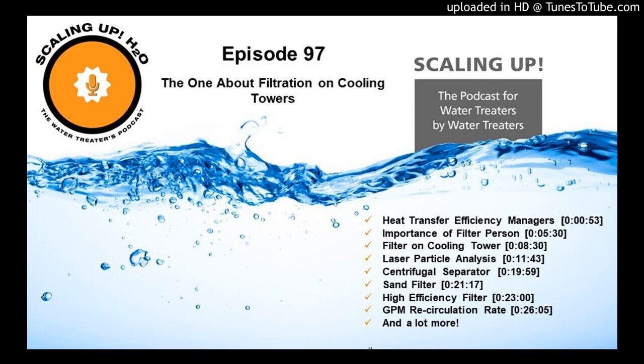And that's a whole different technical problem when you've got significant outside contamination, not from the air. Surface area is another thing. The only reason I make a point of looking at surface area is that when you have really fine particles, the surface area on each particle is significant. And if you push those particles all together into a big particle, the surface area is just the outside of that agglomerated particle. So a big particle in a cooling tower has nowhere near the surface area of 1 million half-micron particles, and bacteria lives on those fine particles. So the more surface area, the more bacteria.